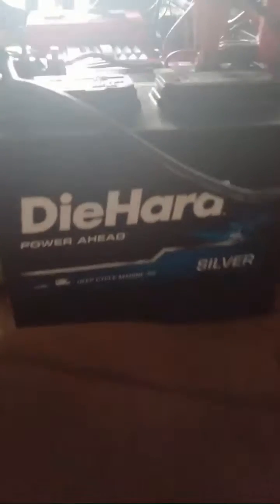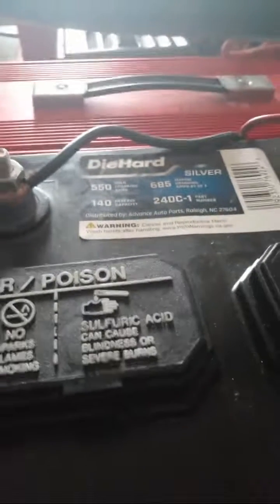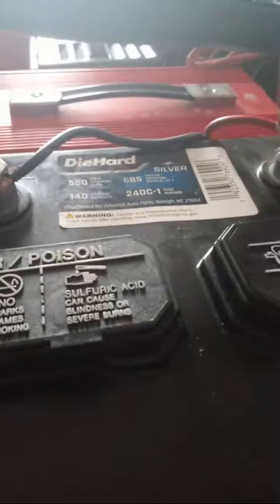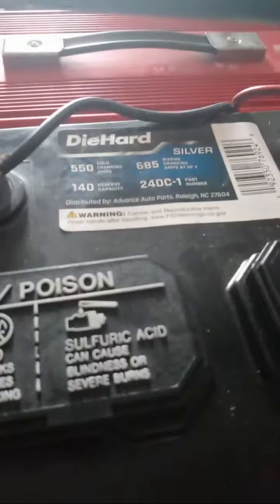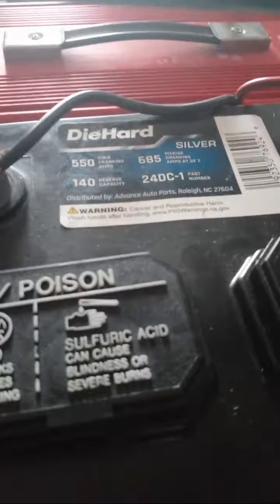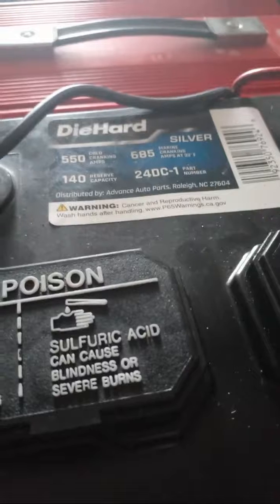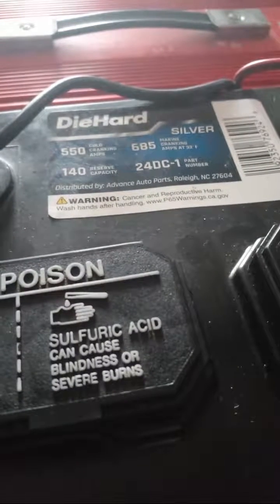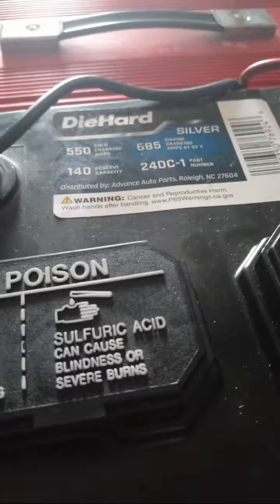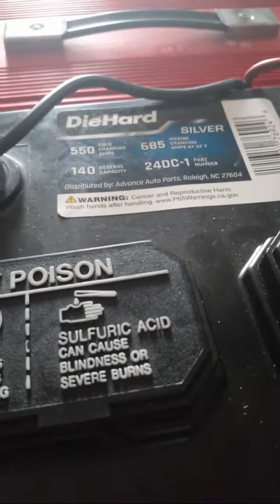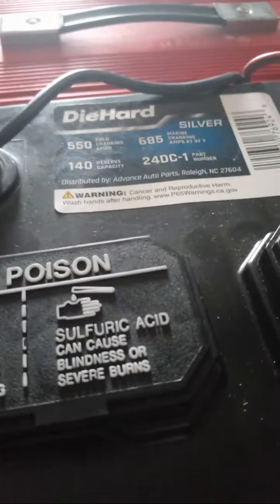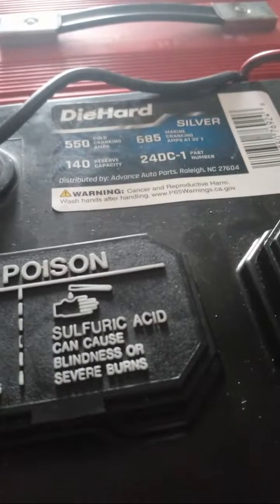So solar batteries will say amp hours right on them. But these hybrid batteries will only give you the reserve capacity. In my real-life experience dealing with these, the most accurate calculation is the third one: take the reserve capacity, multiply it by 60, multiply that by 25, then divide by 3,600, and it will give you the proper amp hour figure for those batteries.